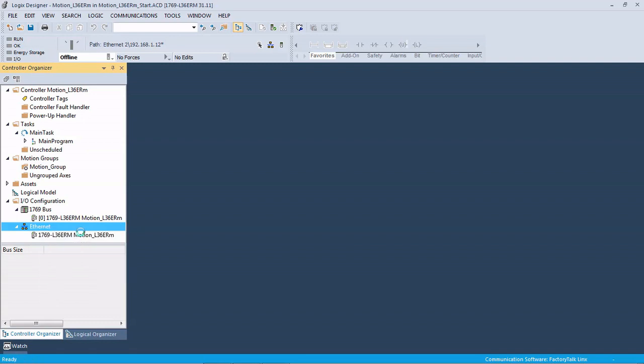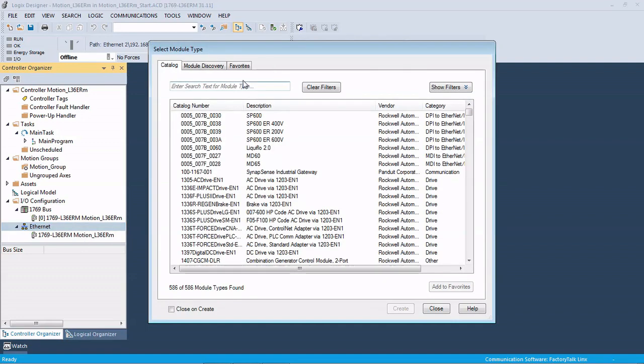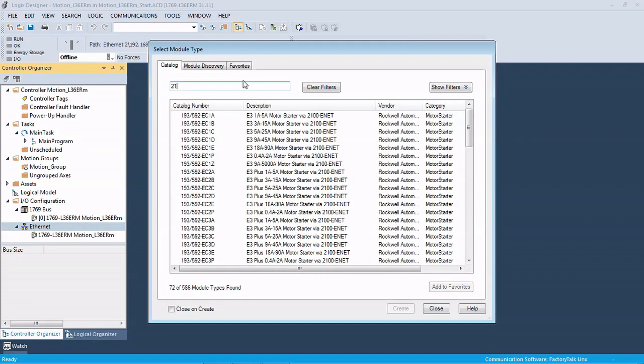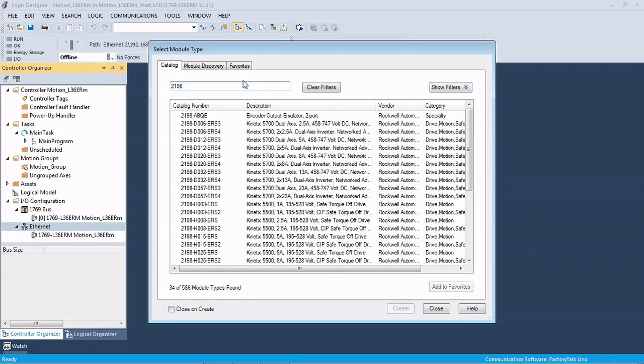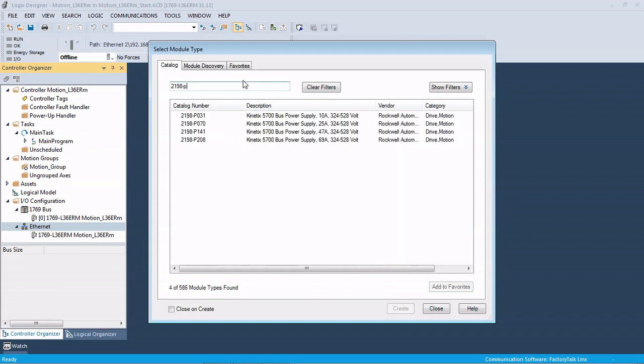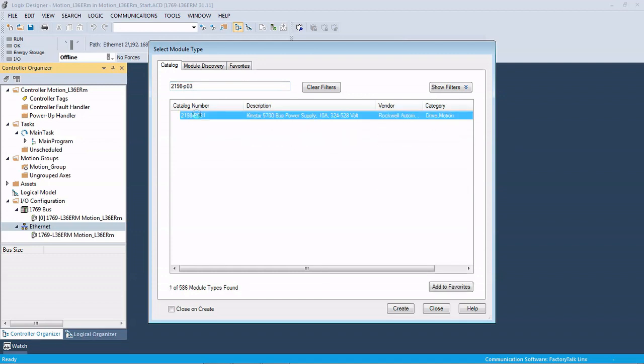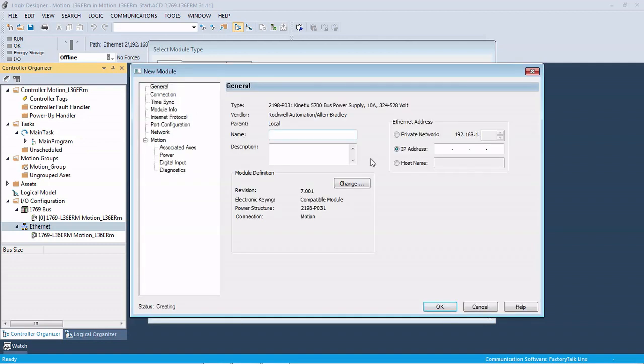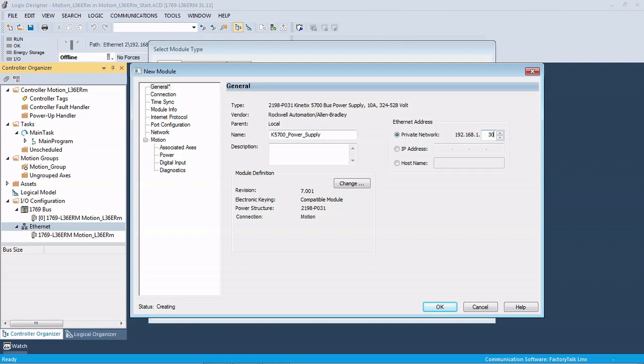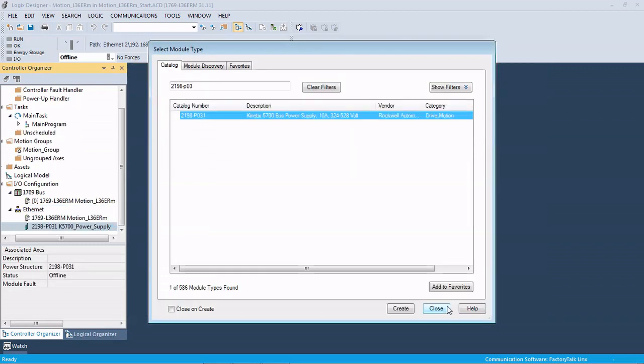We're going to click new module. The first thing we have to add is the Kinetics 5700 DC power supply. In this case we're using the 2198 P031. We're going to add that first and call it K5700 power supply. We have to give it an IP address, in this case we're .30.